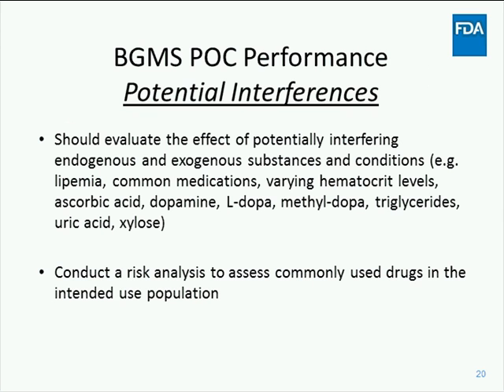The pre-market submission should also include an evaluation of the effect of potentially interfering endogenous and exogenous substances on the device. This study should include common conditions such as lipemia, varying hematocrit levels, as well as common medications. There are certain substances that we know from experience interfere with current meter technology, such as acetaminophen, uric acid, xylose, etc. However, in addition to testing the common interfering substances, we recommend that manufacturers conduct a risk analysis to assess commonly used drugs in the intended use population.